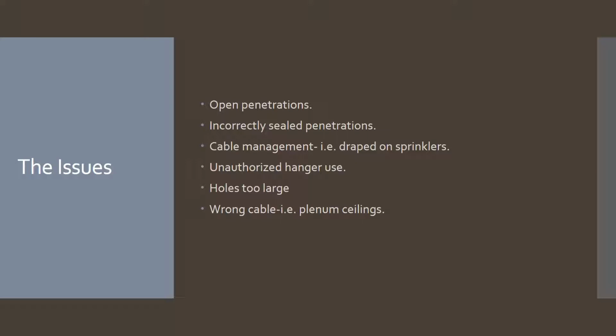Another nuance is wrong cable. There are many places out there, and I'm hearing it's making a comeback to reduce cost, to have plenum ceilings. These are ceilings where there's no enclosed ductwork, where the ceiling itself is the return. If you're going to run cable in ceilings like that, it has to be plenum rated, meaning it has to have a fire rating. If you have a plenum ceiling and you're putting non-fire rated cable in it, that can create an issue in terms of regulations.